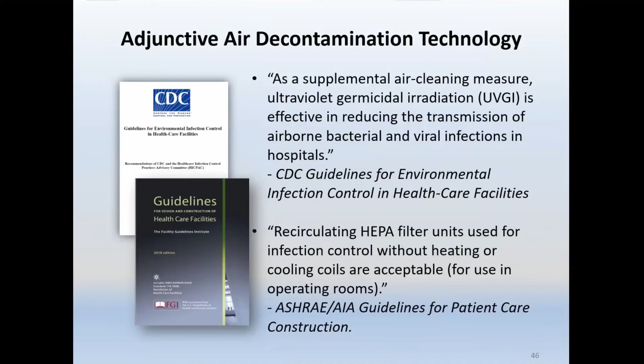But also in ASHRAE guidelines for patient care construction, they state recirculating HEPA filter units used for infection control without heating or cooling coils are acceptable for use in the operating room.